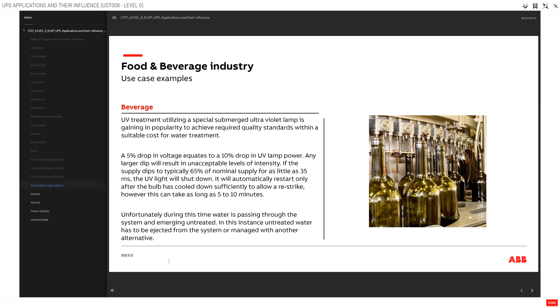If the supply dips to typically 65% of nominal supply for as little as 35 milliseconds, the UV light will shut down. It will automatically restart only after the bulb has cooled down sufficiently to allow a restrike, however this can take as long as 5 to 10 minutes. Unfortunately, during this time water is passing through the system and emerging untreated. In this instance, untreated water has to be ejected from the system or managed with another alternative.